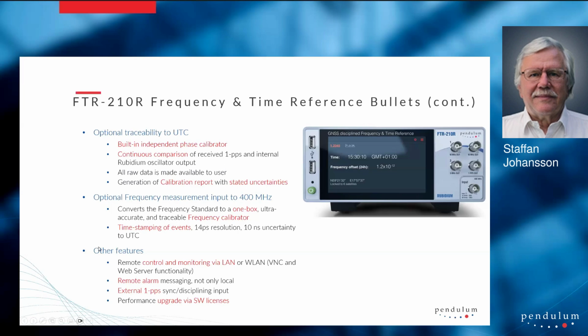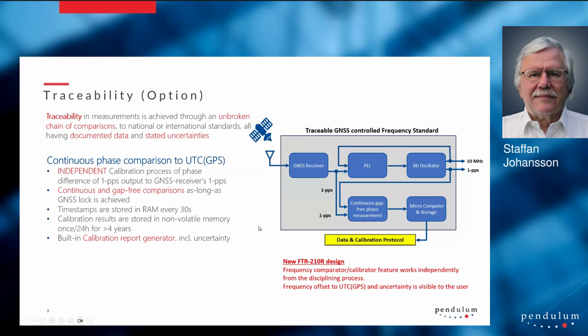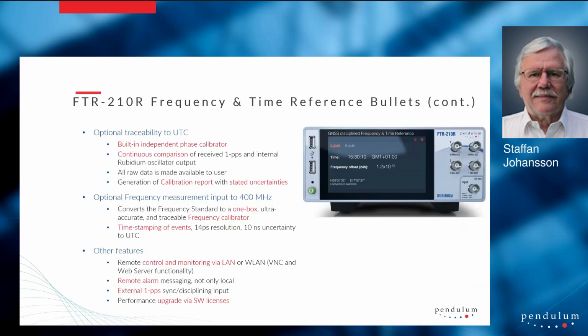Another important feature of this unit is an optional frequency measurement input up to 400 MHz, which converts the frequency standard to a one-box frequency calibrator. That means you have both the time interval counter needed for calibration and the frequency reference inside one box, of course.